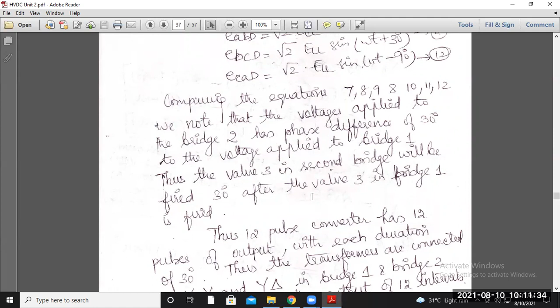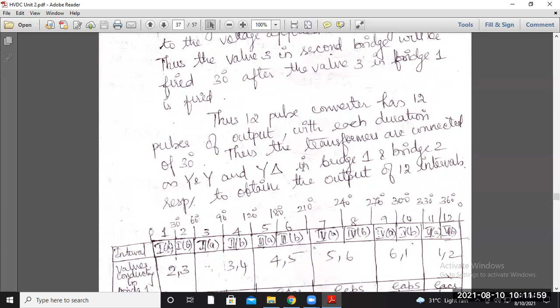The 12-pulse converter has 12 pulses of output, whereas in the 6-pulse converter we studied 6 output pulses. Here, the 12-pulse converter has 12 pulses of output, each with a duration of 30 degrees. Thus, the transformers are connected as star-to-star and star-to-delta, as discussed for bridge 1 and bridge 2 respectively, to obtain the terminal output, which is given in this format.